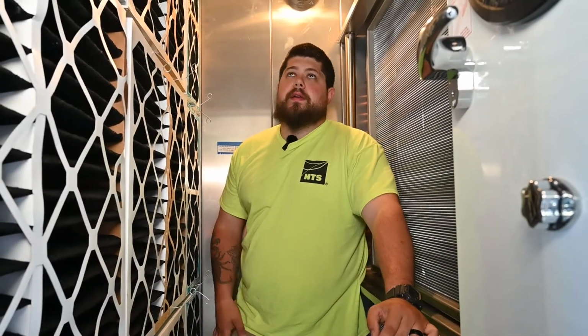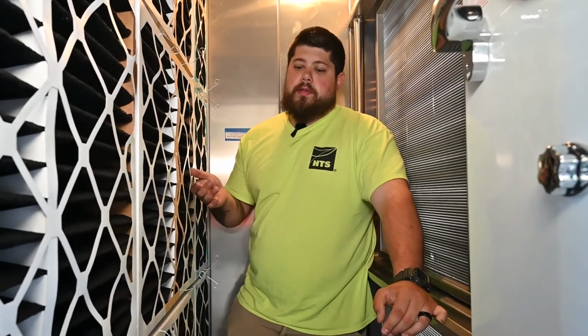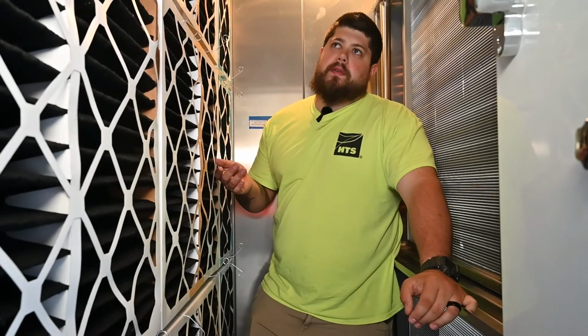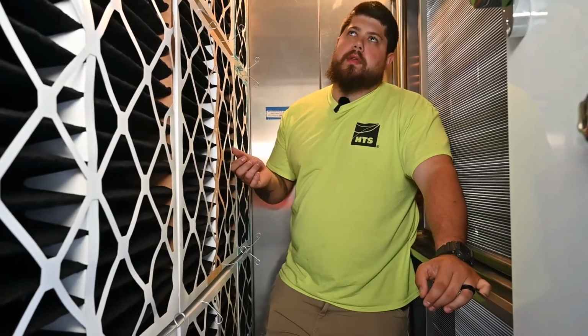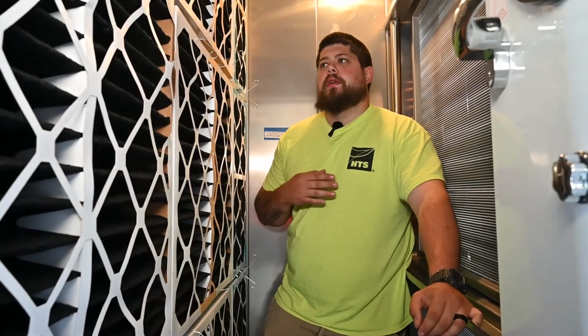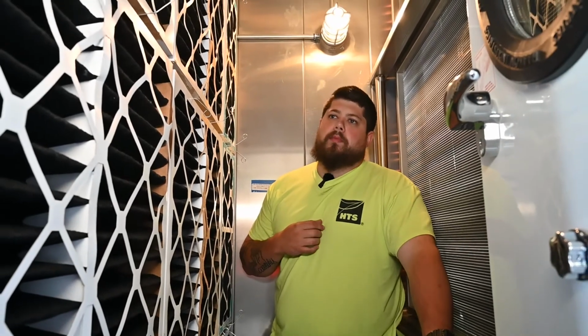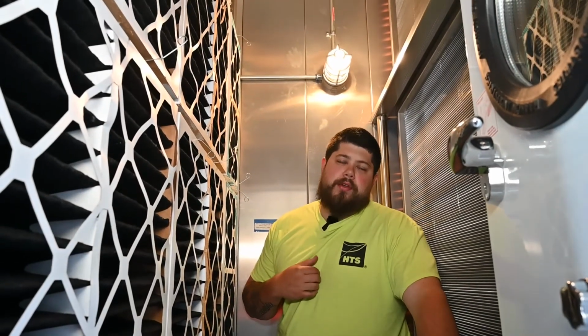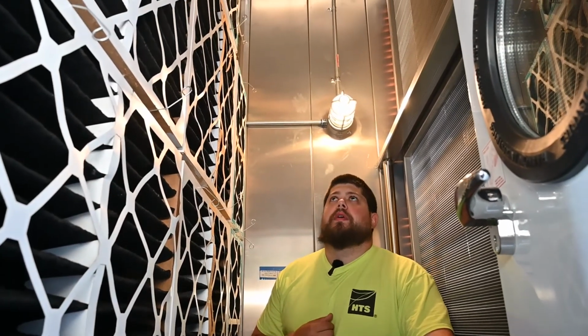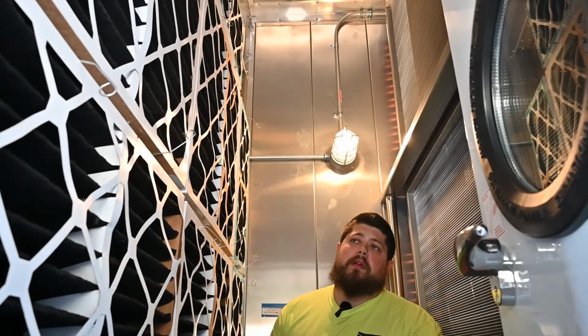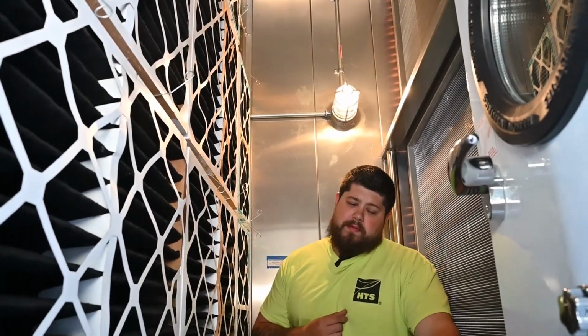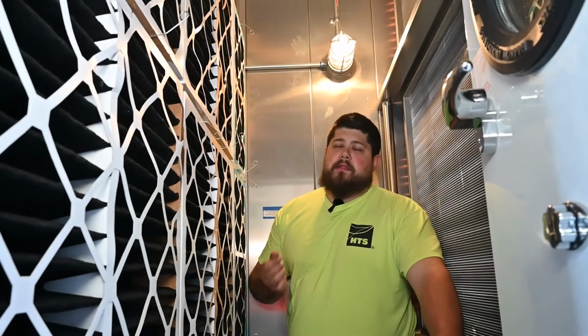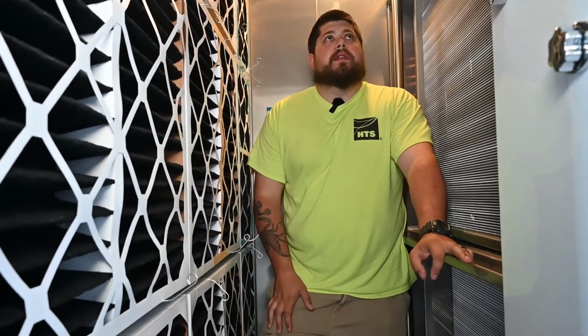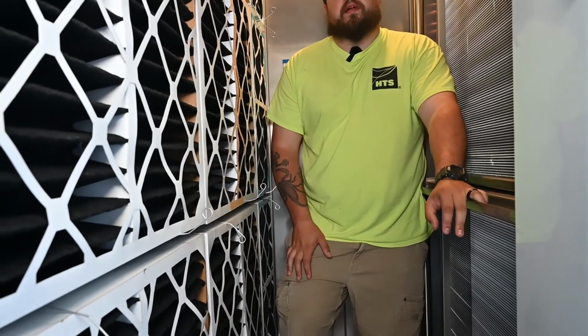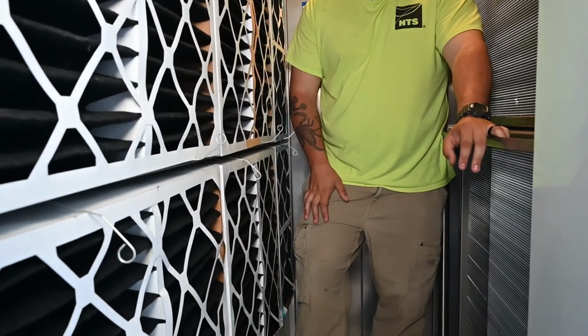So this section here is for our pre-filters. These are charcoal filters. They're a little more controlling than your normal filters. The recommendation of replacing filters is going to be strictly based off of location. I can say every 3 months I recommend changing these, but I've found that every location is most definitely different compared to what I can recommend.